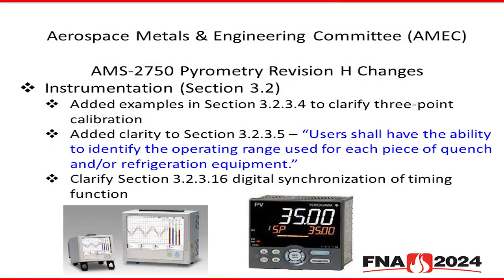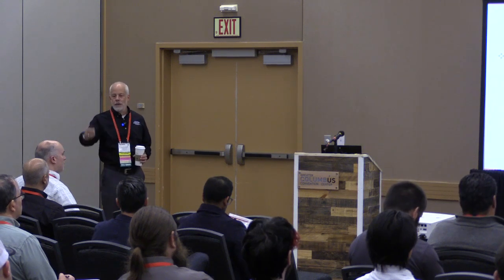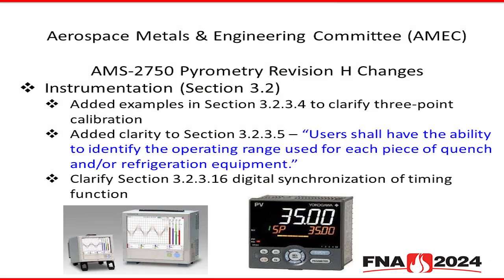Again, added some more examples in Section 3.2 for clarification of the 3-point calibration. We had to address situations where you have a defined qualified operating range, like a furnace, 300 to 1200 degrees, you check 3 points, 300, 1200, and a midpoint. Well, how about a quench system for aluminum quenching? You don't really have a defined qualified operating range. So instead of us defining it for you, we gave that power back to you guys. You define the range you want to calibrate that equipment in. That's where we're trying to let the suppliers choose some of this stuff versus us mandating the requirements.